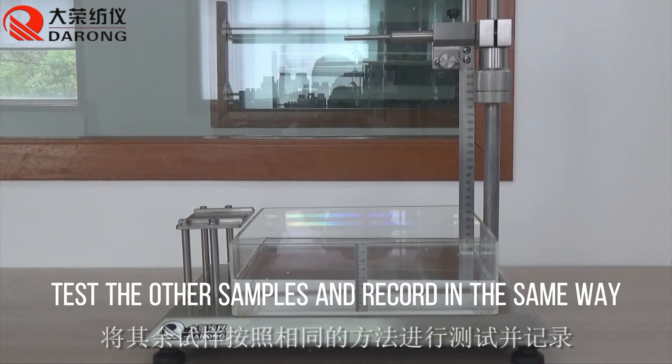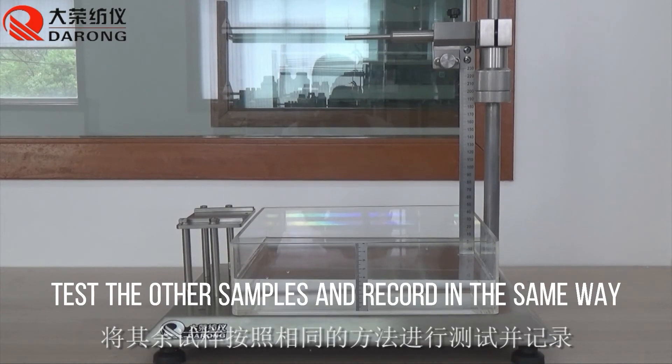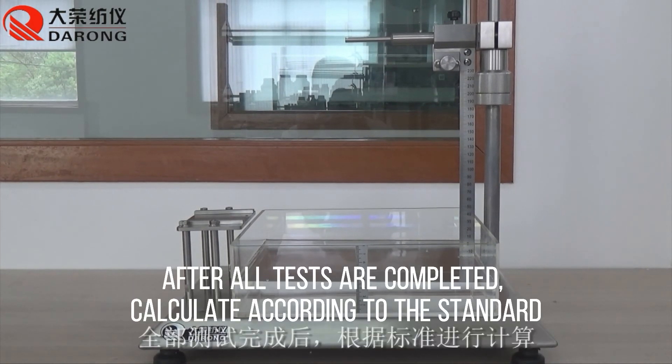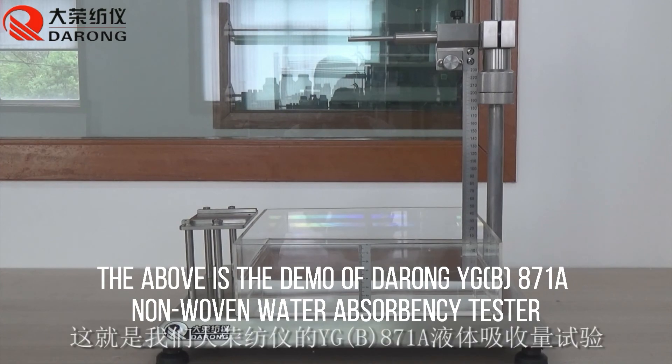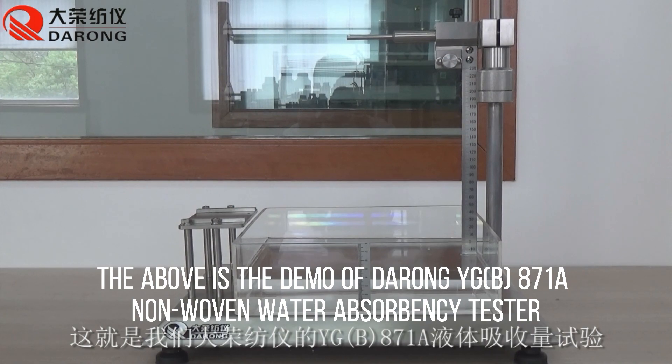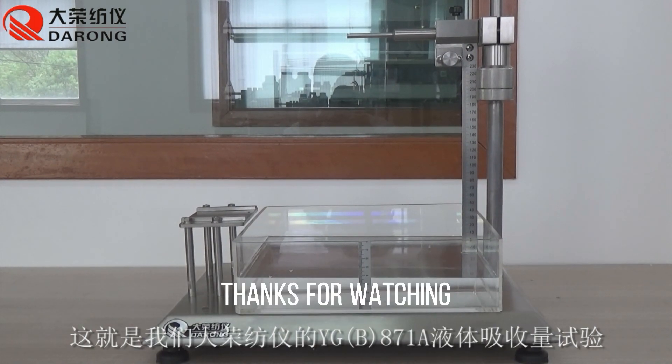Test the other samples and record in the same way. After all tests are completed, calculate according to the standard. This concludes the demo of the Darong YG(B) 871A non-woven water absorbency tester. Thanks for watching.